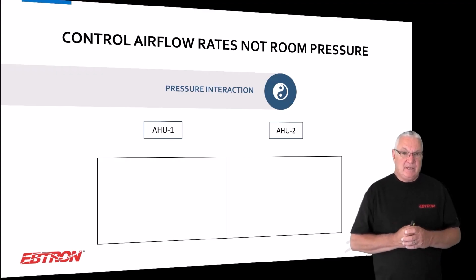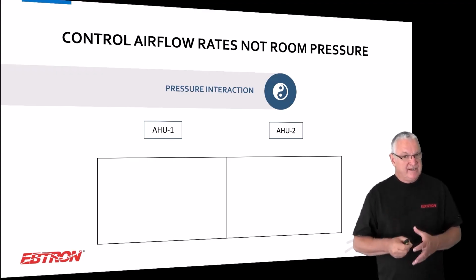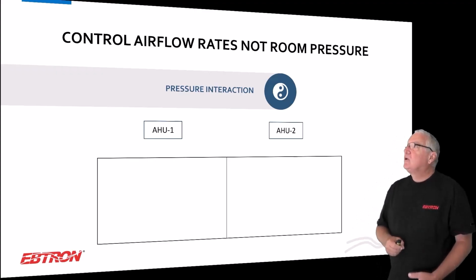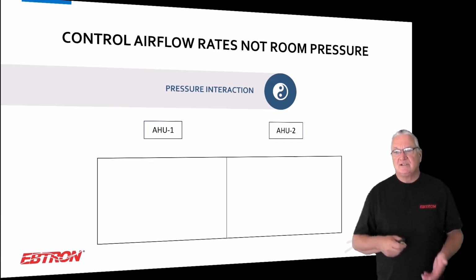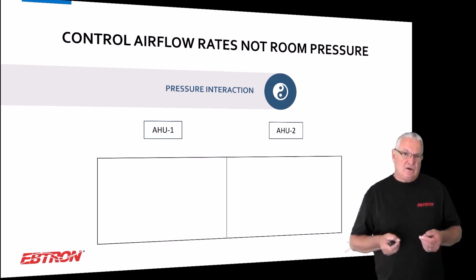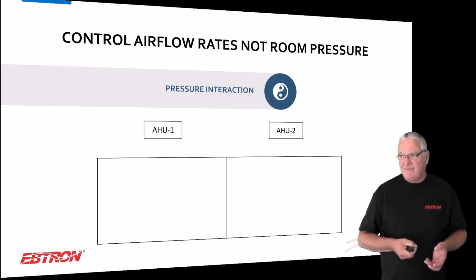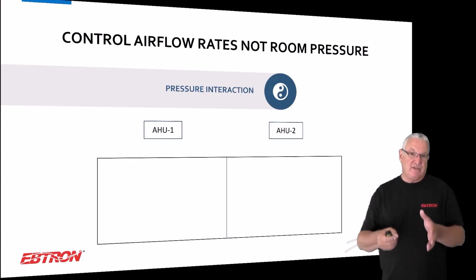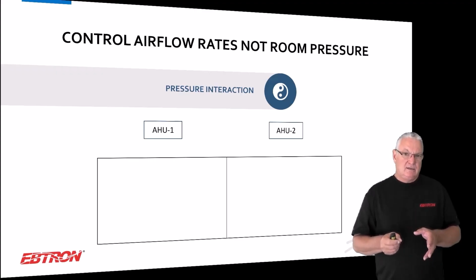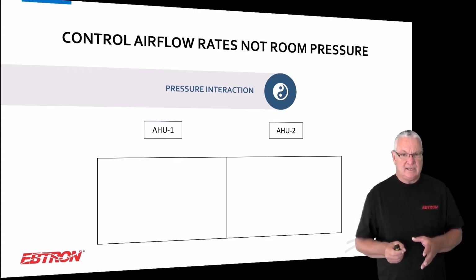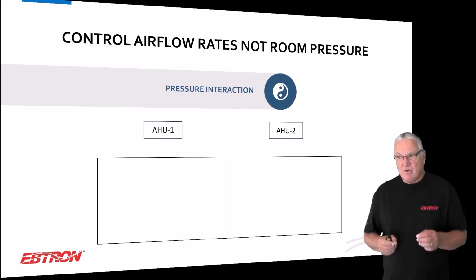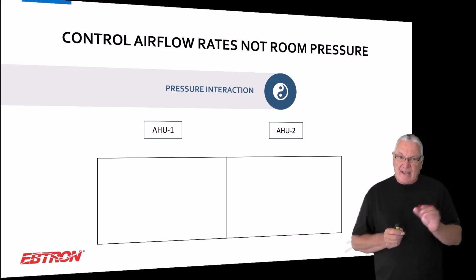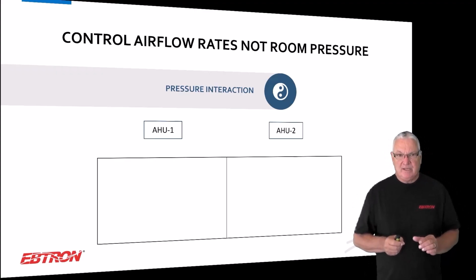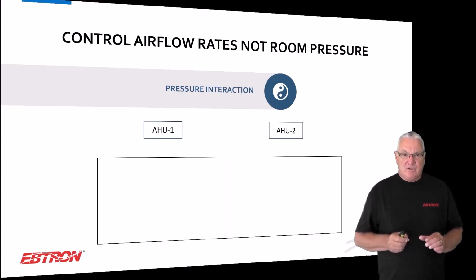And because of this one serious flaw, forget talking about the pressure sensor and does it drift, and forget talking about the pressure sensor and is it affected by wind pressure, because really you want to isolate mechanical pressurization, okay? So wind pressure and stack pressure, don't isolate that, all right?